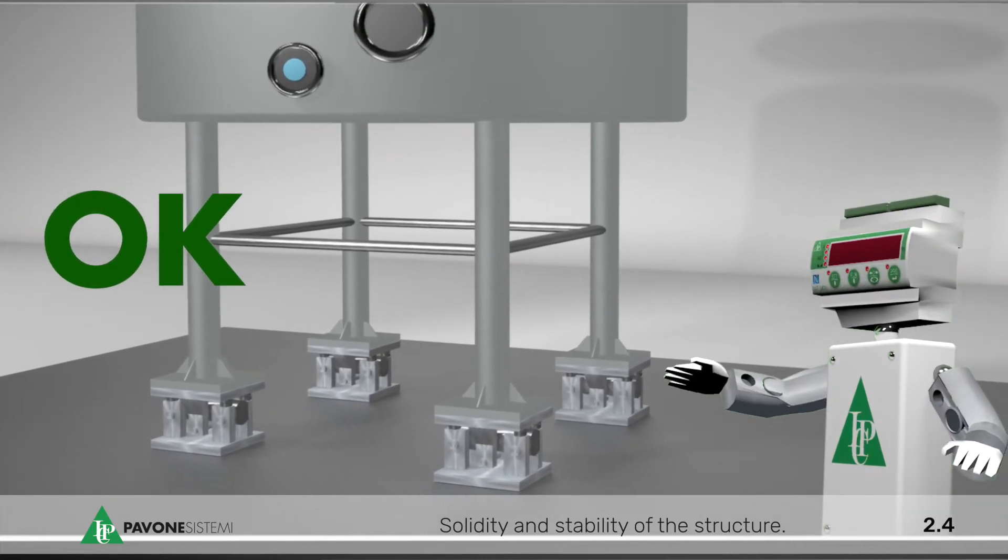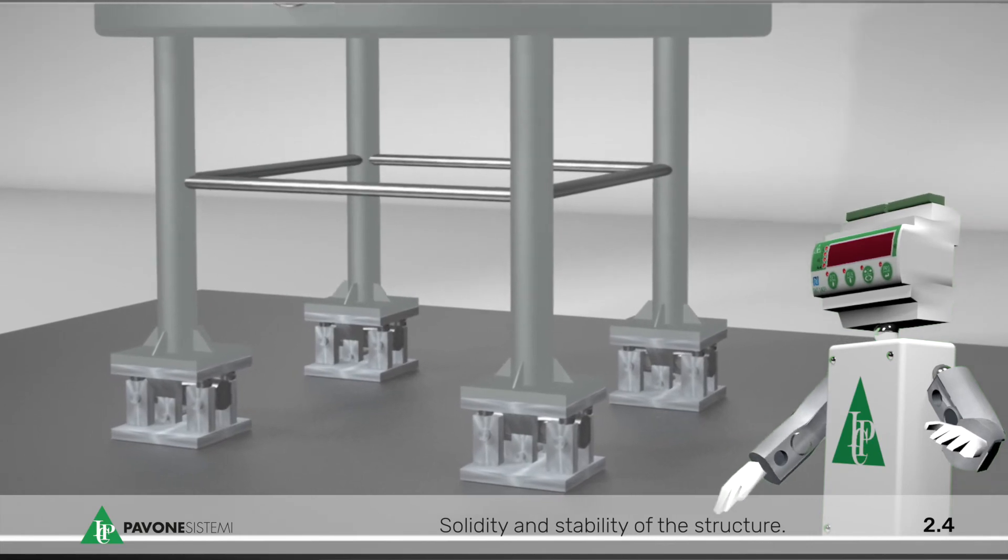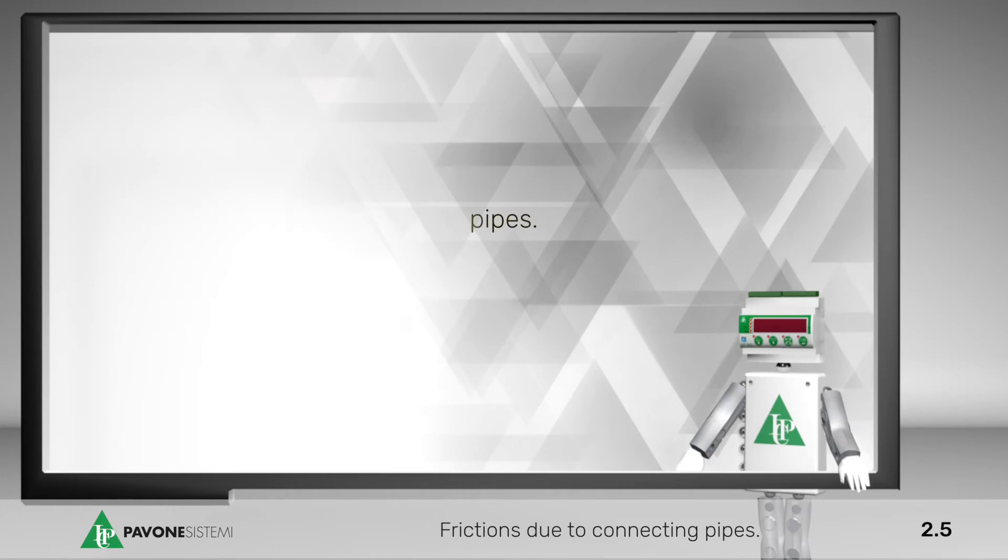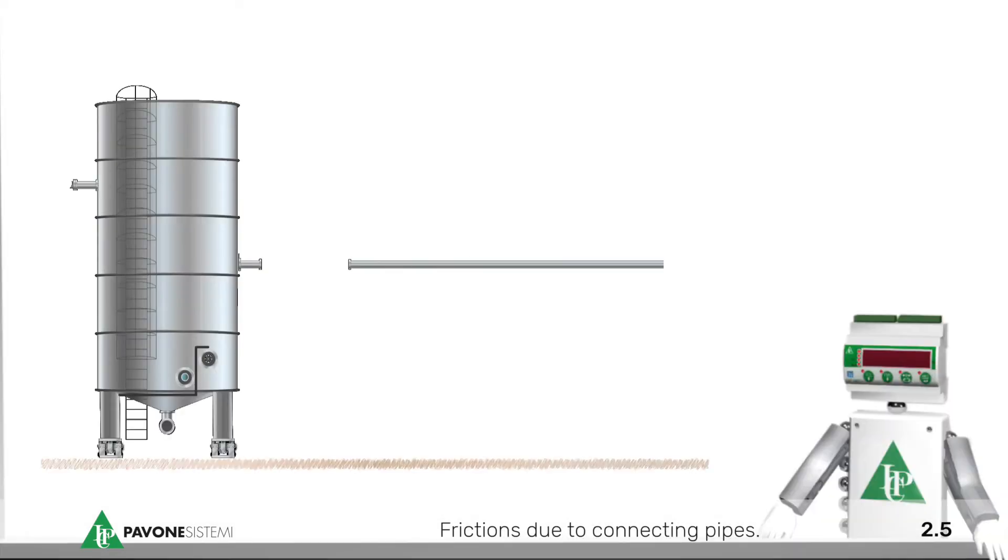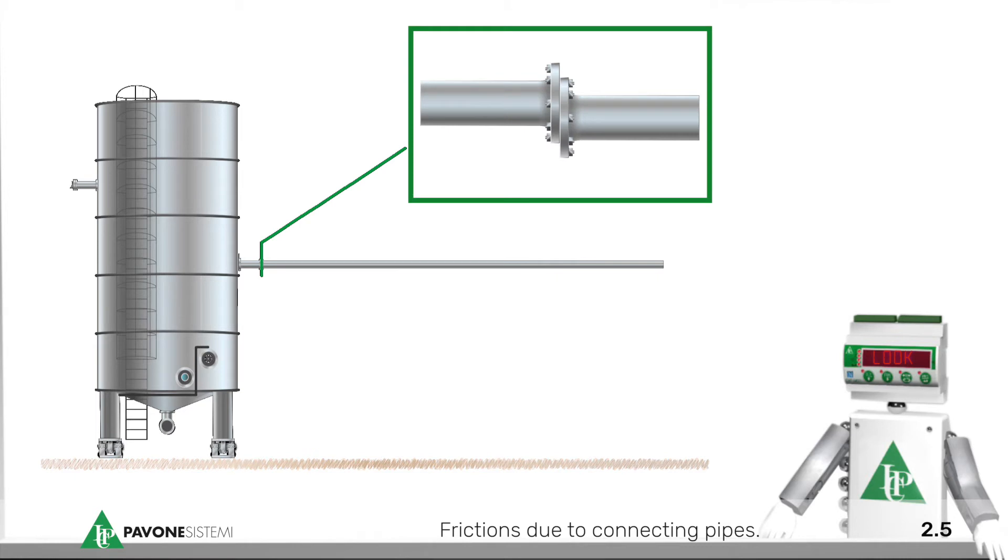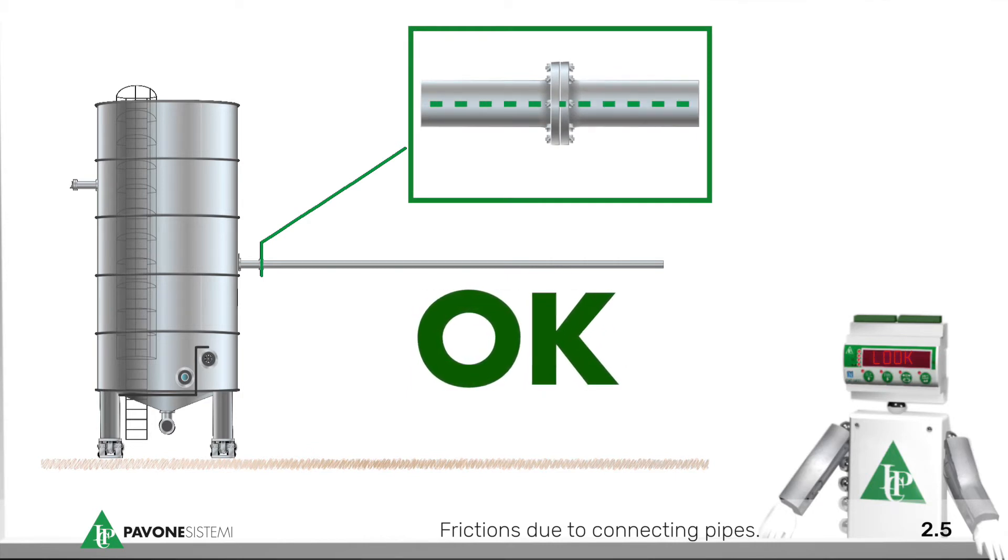Frictions due to connecting pipes. The more a weighing structure is free from friction, the more the weighing system is precise. When piping are present, make sure that the pipes that have to be anchored to the weighing structure are closed and aligned to the nozzle to which they will be clamped.